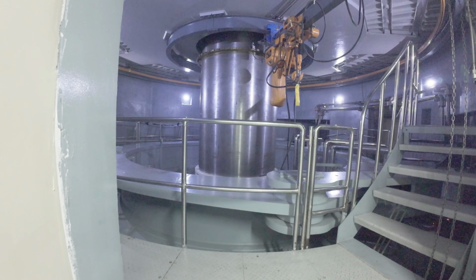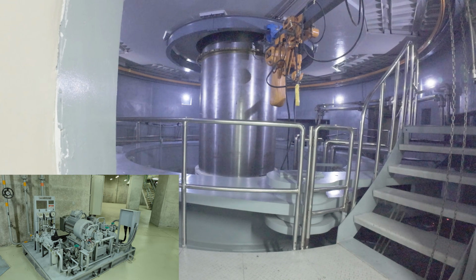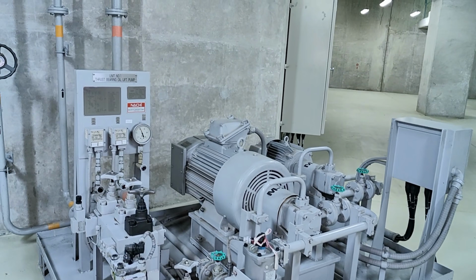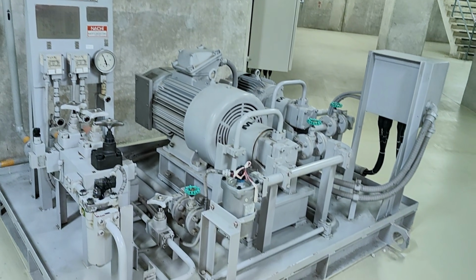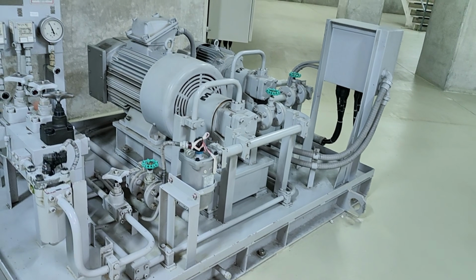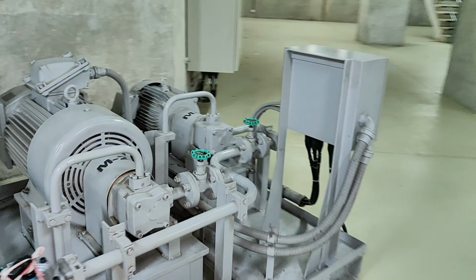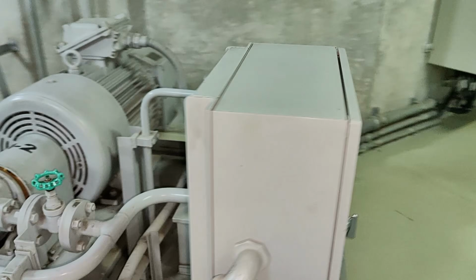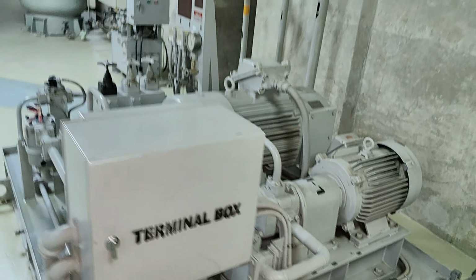Okay, now the valve is open. The water path is ready. Everything looks prepared for startup, but the turbine still doesn't move. Why? Because before a giant machine can start spinning, it needs a little help first. Hidden beneath the turbine is a system most people never see. It is called the oil lifting system. The turbine, shaft, and the generator together weigh hundreds of tons. Starting all that weight directly on the bearing would create a lot of friction. So engineers use this oil pump, which delivers oil at 28 liters per minute with a pressure of 13.7 megapascal. This oil is pumped underneath the bearing surfaces. The pressure creates a very thin layer of oil that slightly lifts the rotating part.